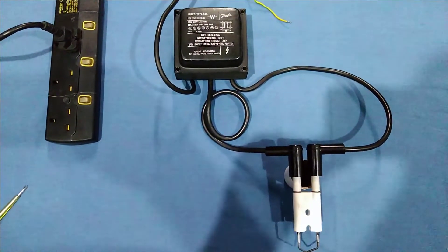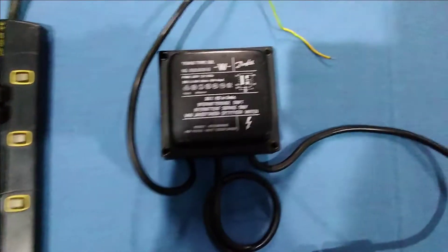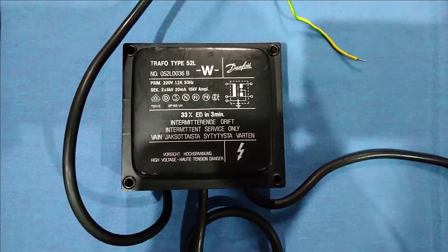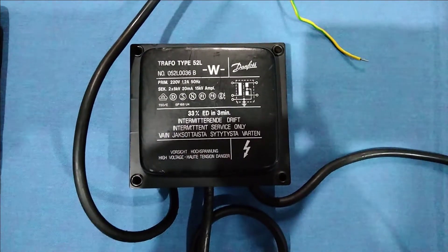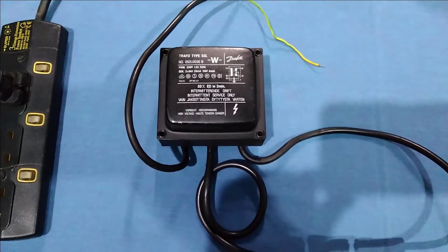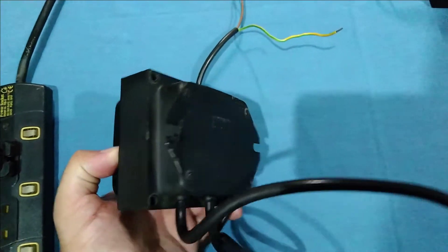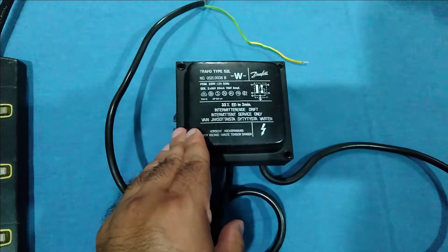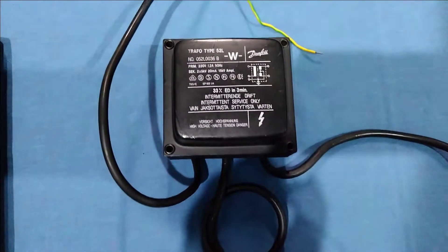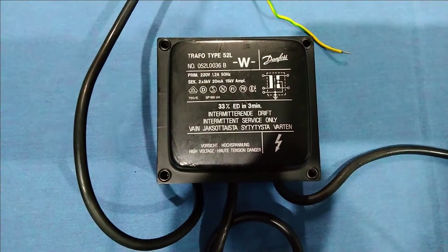In this video we are going to show you the working of this Danfoss Trafo ignition transformer. It is a Trafo Type 52L ignition transformer and its manufacturer code number is 052L0036 B. It's a metal body ignition transformer and it is quite heavy — its weight is almost 2.165 kg. You can see its back side here as well. Its primary voltage is 220 volts 50Hz.